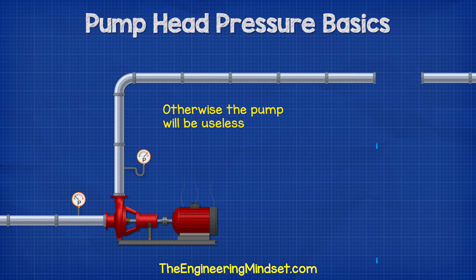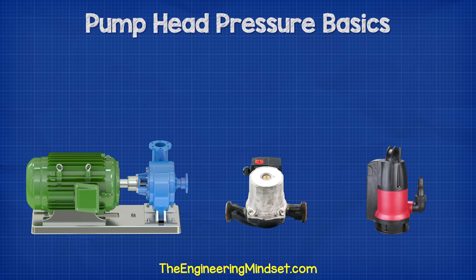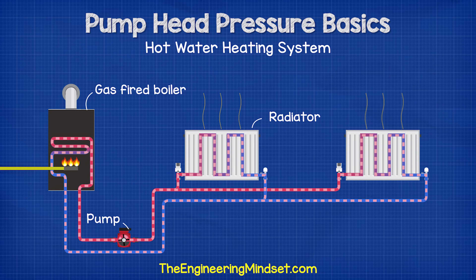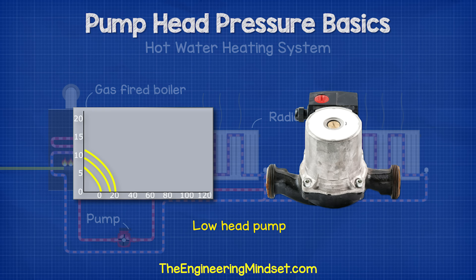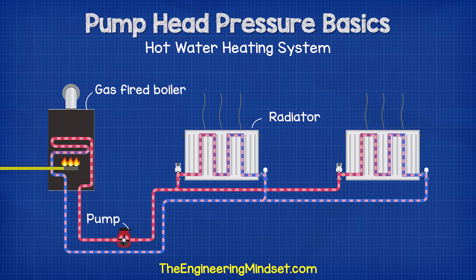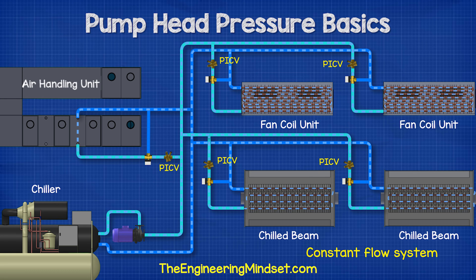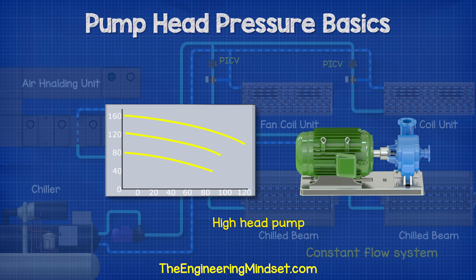Otherwise, we're not going to get any liquid out the other end. When we look at pump charts, we'll find pumps ranging in head and flow rate. For example, when we look at a small domestic heating system with a few fittings and short pipes, we would use a pump with a relatively low head pressure. But if we were to look at a commercial heating system with multiple air handling units, fan coils, and long pipe lengths, then we know the pressure drop will be much higher, so we would need a pump that can provide much more head pressure.